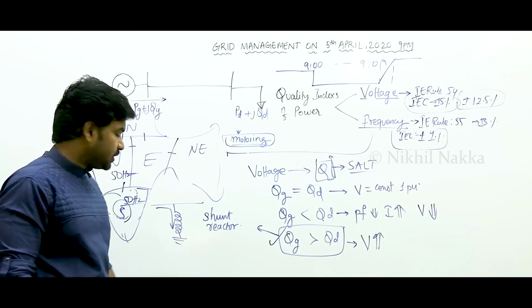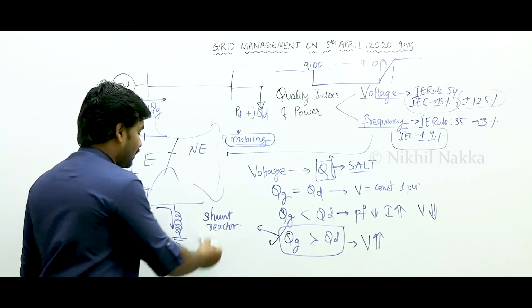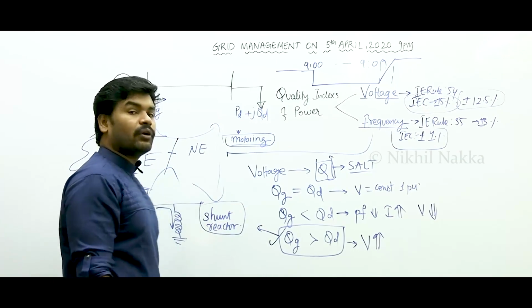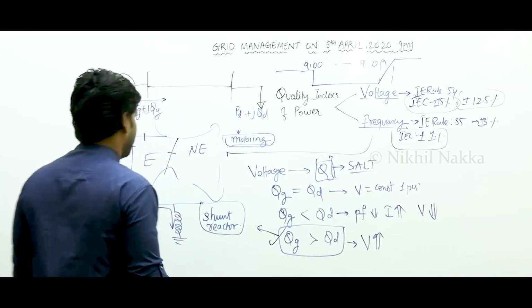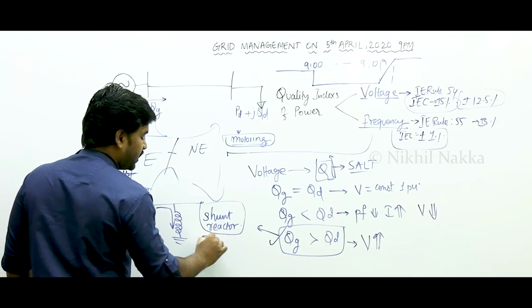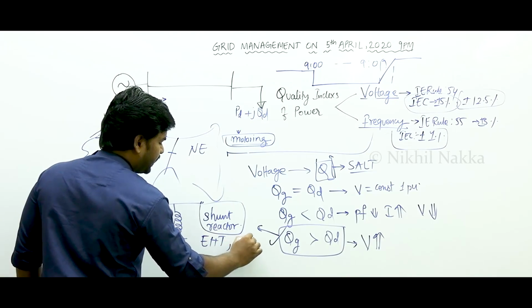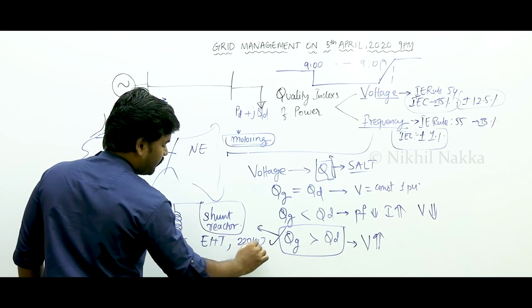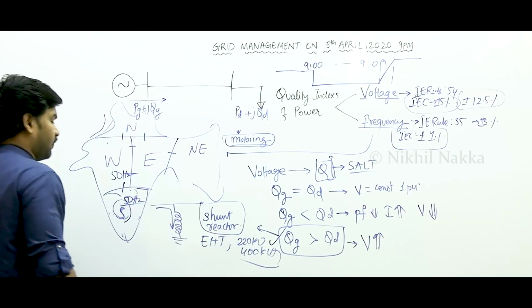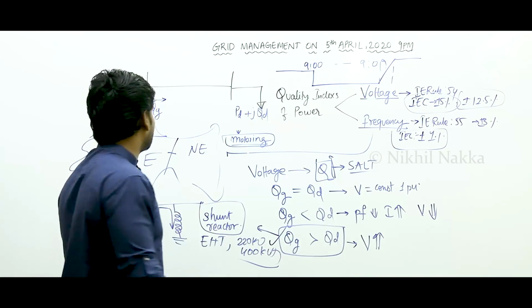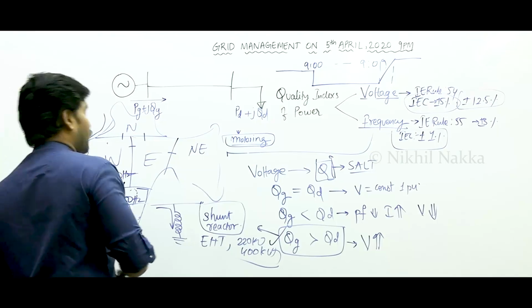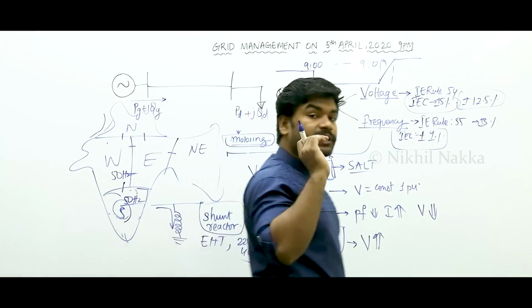Now the next question is, where is the location of these shunt reactors? These shunt reactors are basically present in the EHT substations, generally at 220 kV in some places and 400 kV in most cases - strategic points for having these shunt reactors. Why is it so? For this we have to understand the voltage profile of the line.